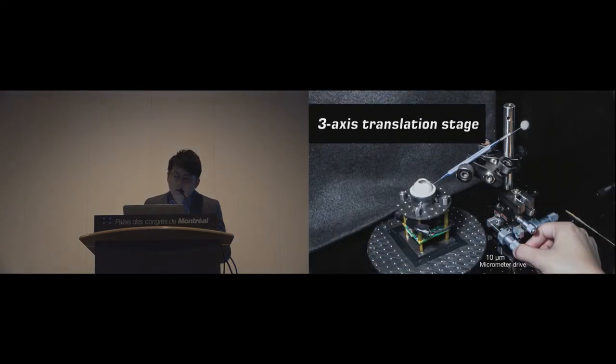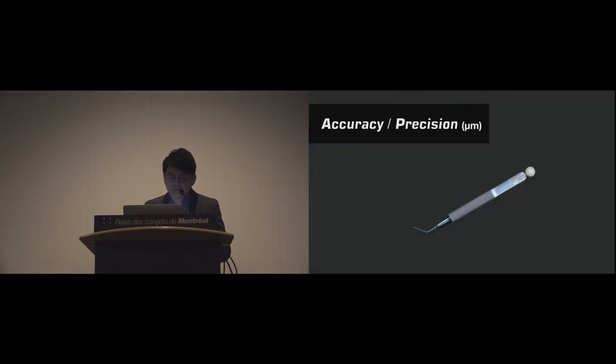System evaluation. We use a three-axis linear translation stage with micrometer drives to evaluate the tracking accuracy and precision of the system. The system accuracy of the tip and the end were 20 and 59 micrometers, respectively.